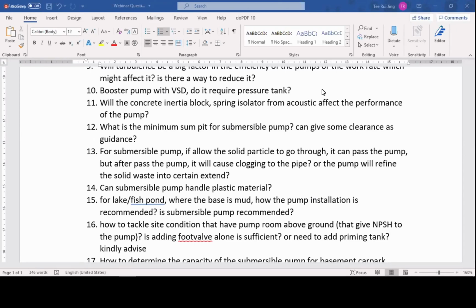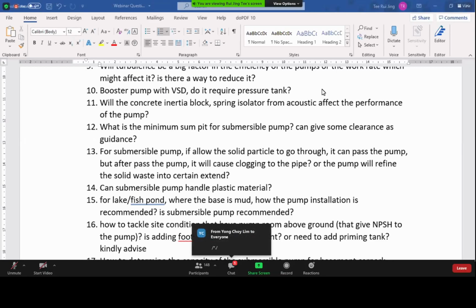Now, if you compare it to the old conventional pneumatic systems, you need a very big tank because you want to control the start-stop of the pump. So the pneumatic tank actually acts as a buffer to prevent too much start-stop. Now, in a variable speed system, the pumps do not start and stop anymore, but adjust the speed. So that means the function of that pneumatic tank is greatly reduced. But we still put a small pressure tank. The reason is to absorb some pressure fluctuations in the water itself, because we have a pressure sensor at the discharge pipe, and that pressure sensor reads the discharge pressure of the pump.